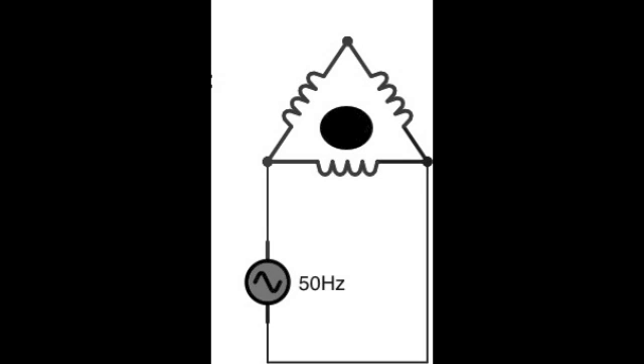When there's no capacitor or a too small capacitor connected it will not have any starting torque because if there's no capacitor connected there will just be a reversing magnetic field between the live and neutral connection and the rotor will just stay where it is.